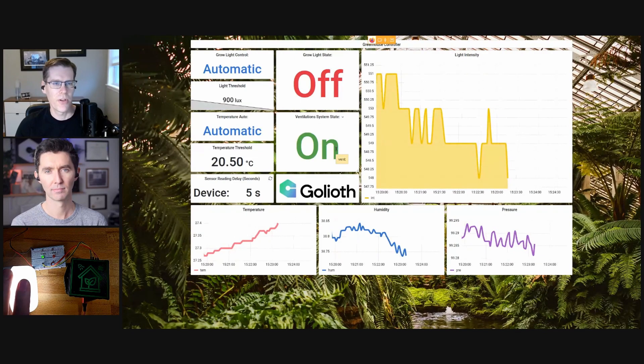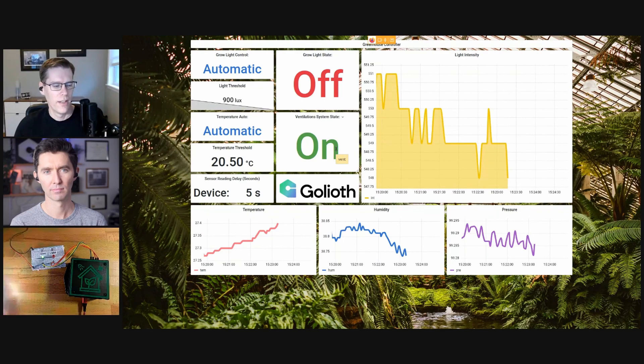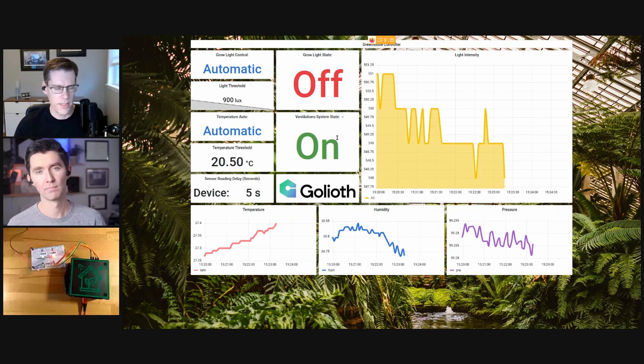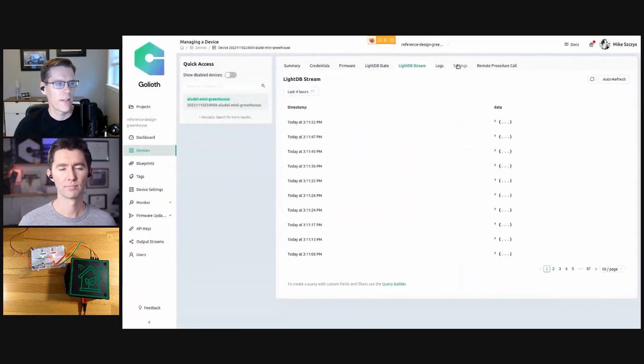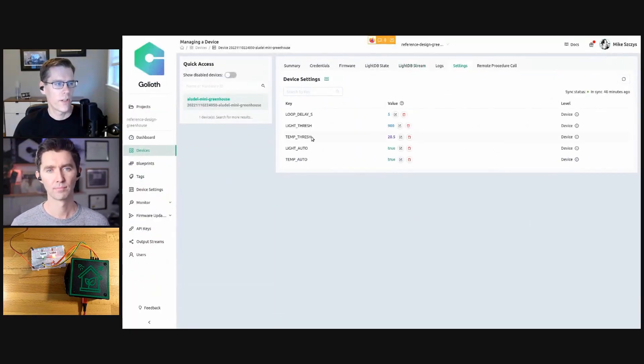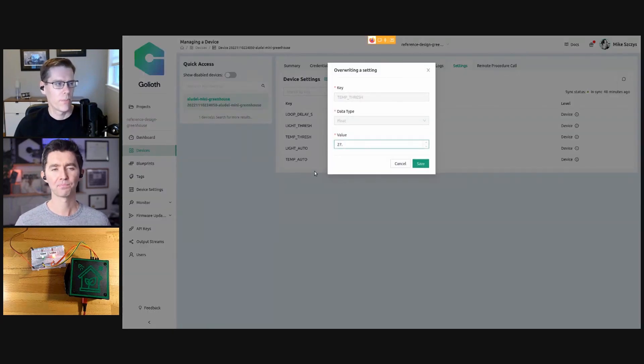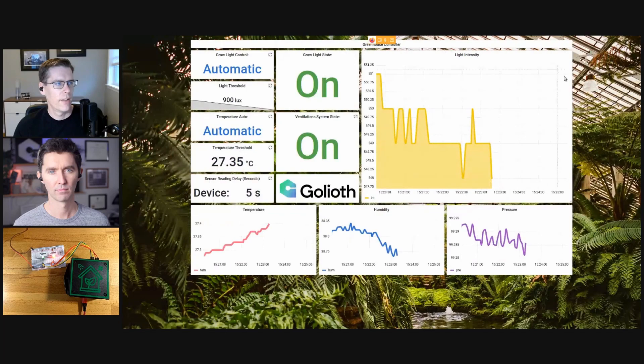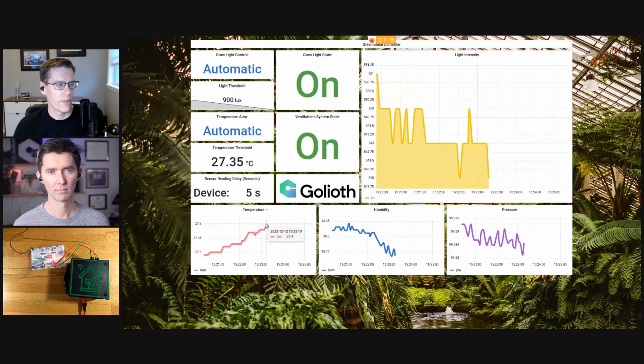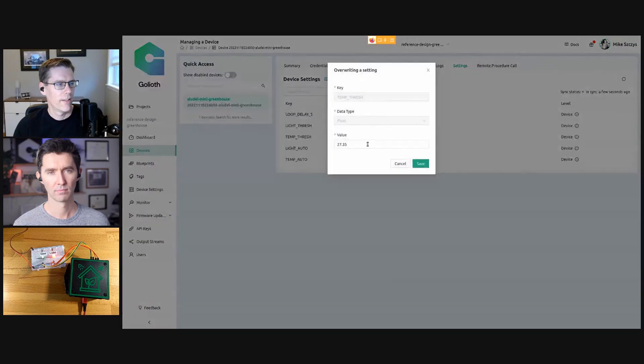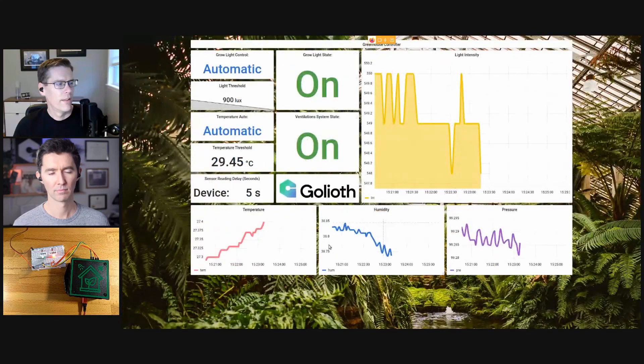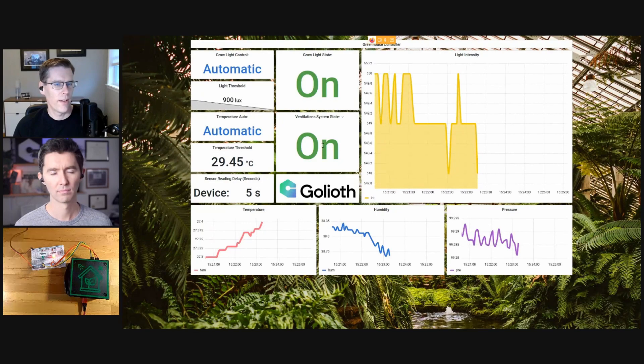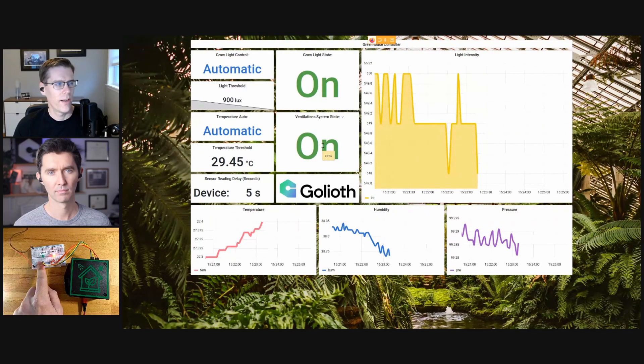Normally I'd put my finger on the temperature sensor, but it's enclosed in the case, which gives a little isolation from small temperature changes. What we can do is go to the settings on our Golioth dashboard and change our threshold. For this particular plant, let's say it can get to 27.35 degrees Celsius. If we switch that and go back to the dashboard, the ventilation system should turn off. Let's set it to 29.45 — and we should see that ventilation system go off, and the light on our demonstration model just went off.